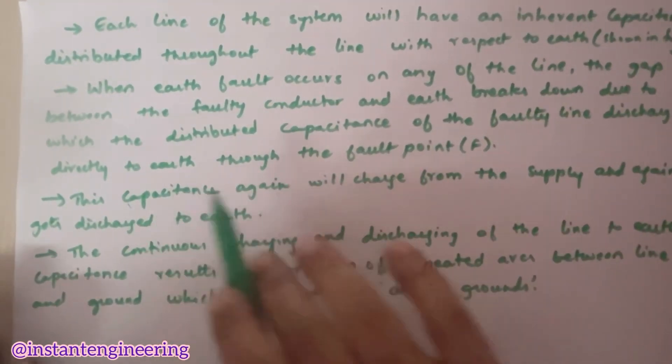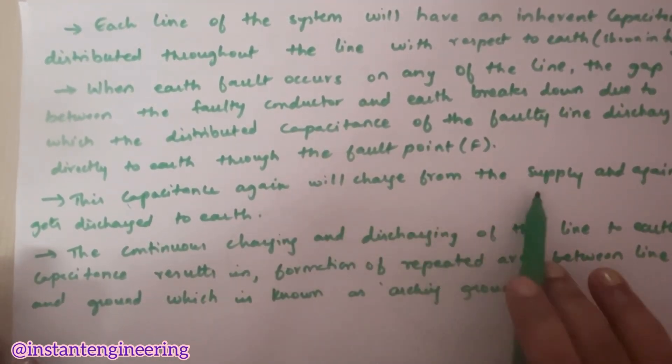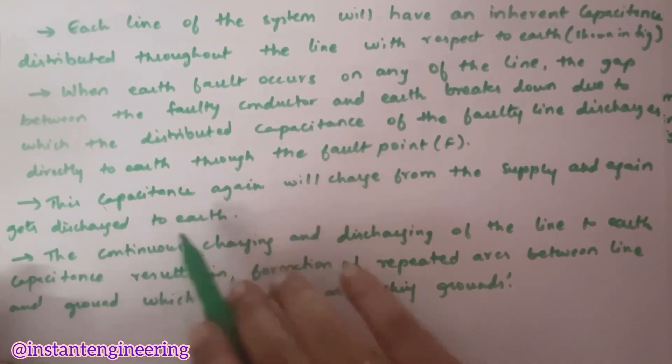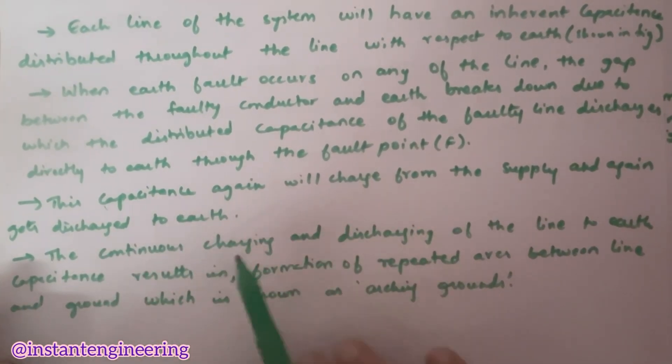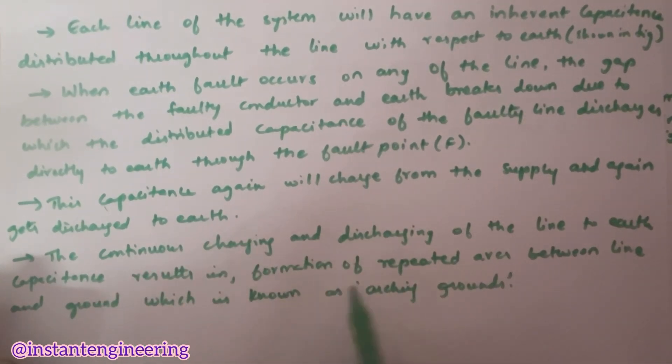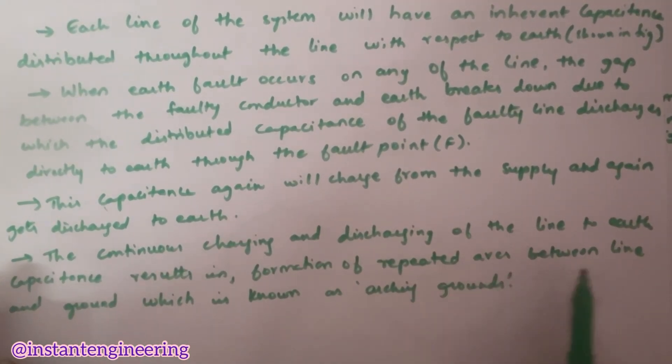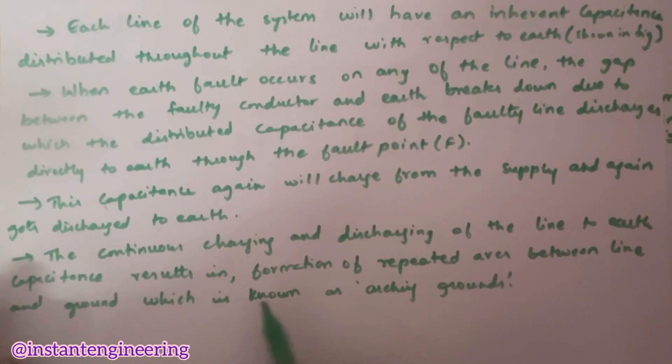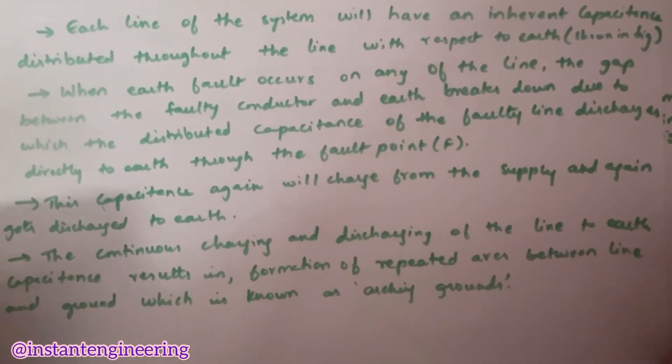This capacitance again will charge from the supply and again gets discharged to the earth. The continuous charging and discharging of the line to earth capacitance results in formation of repeated arcs between line and the ground, which is known as arcing grounds. Now, I will clearly again explain you.